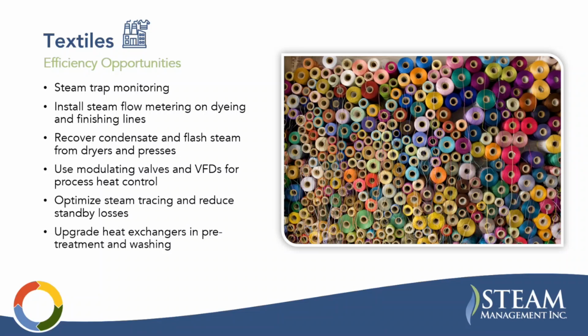Efficiency opportunities here: steam trap monitoring. Any of these manufacturers with high run hours, high pressure steam lines - not super high pressure compared to power generation, but medium pressure, not a 5-10 pound steam system - steam trap monitoring starts to make sense in these facilities. A lot of these manufacturers, if they don't have fuel as a byproduct, are just purchasing gas, so they have a pretty healthy fuel cost from an efficiency opportunity perspective.